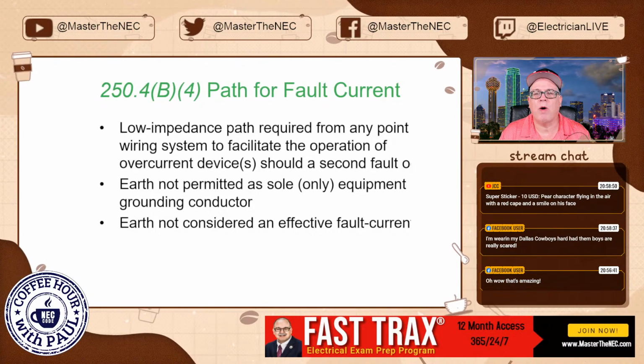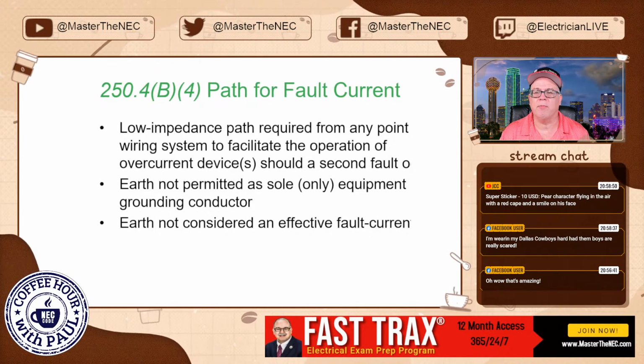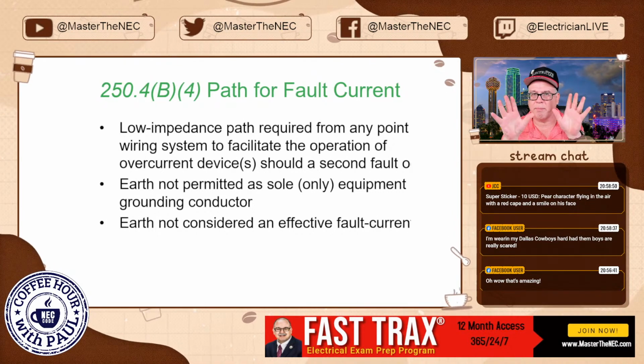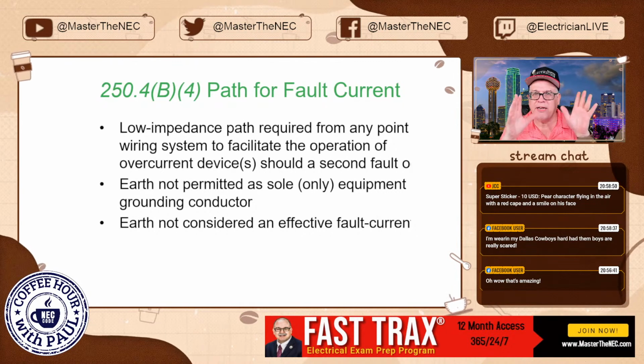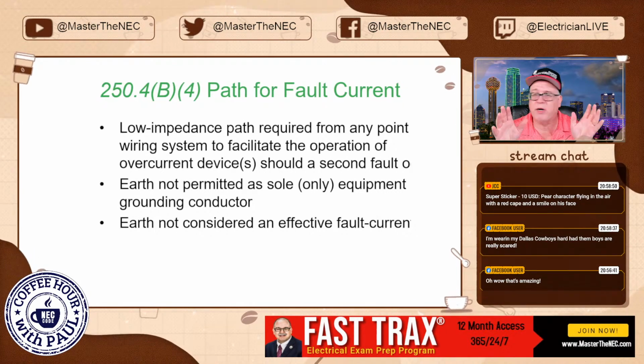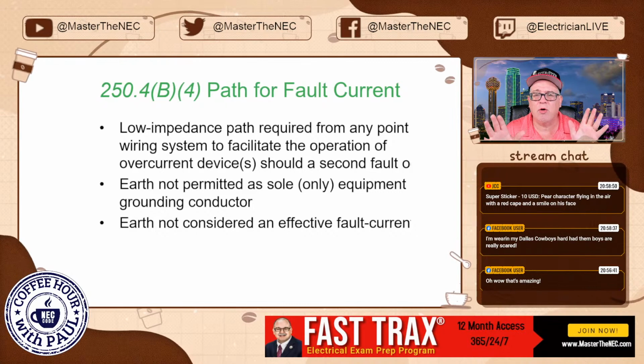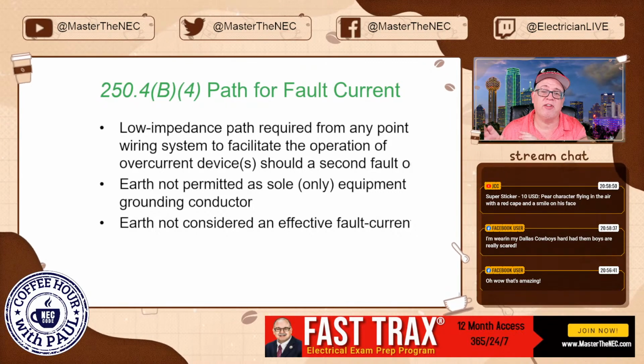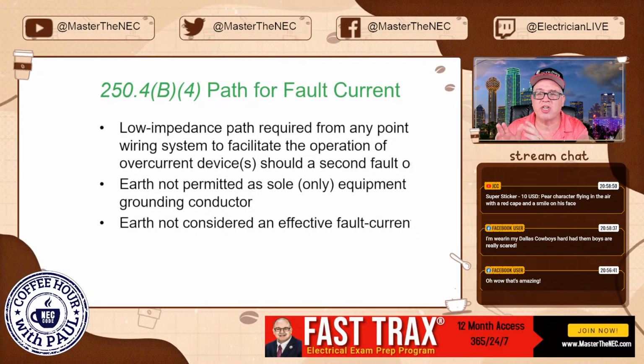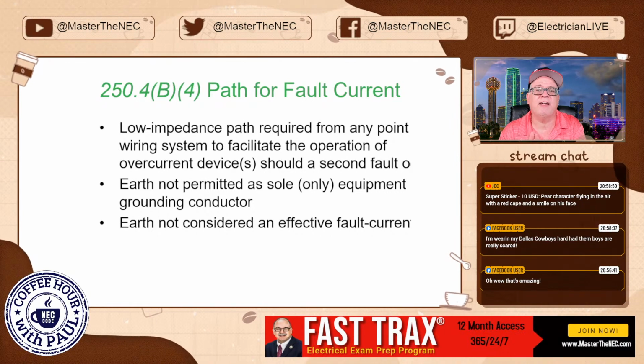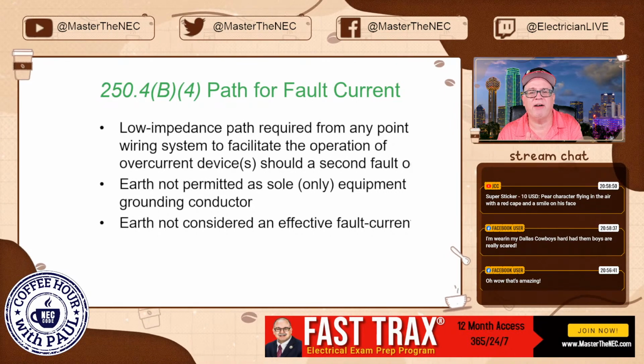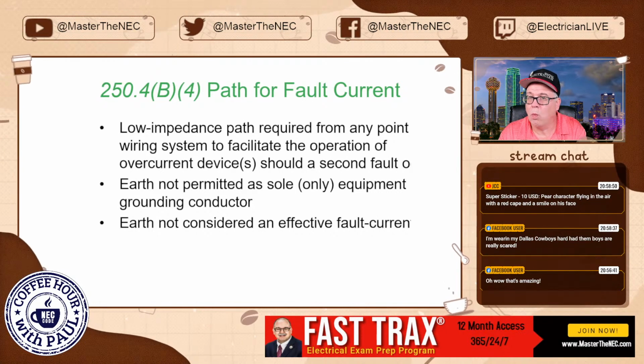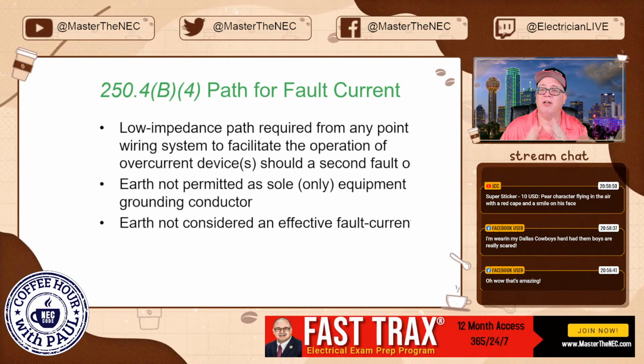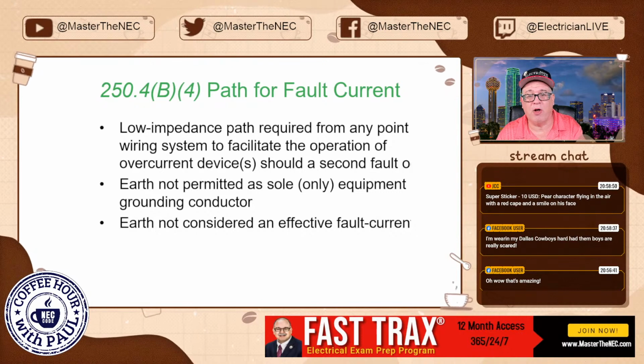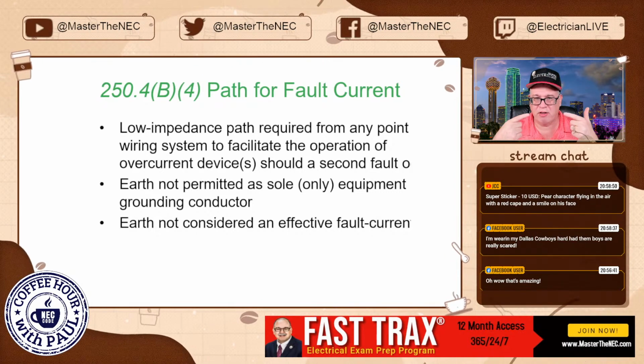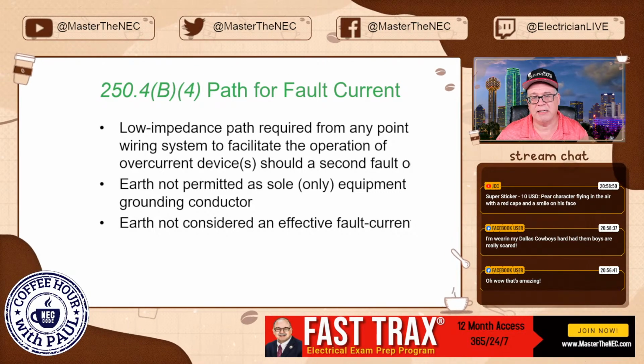Low impedance path required from any point on the wiring system. That's why we're tying it all together. That's why we're using proper couplings, proper fittings, wrench tight, proper connections, bonding jumpers where necessary. Providing that low impedance path at any point on the system, if there's a fault condition, then what happens? It facilitates the operation of the overcurrent device, but only when a second fault occurs. In the first fault, we should have some type of monitoring system for these ungrounded systems, right?